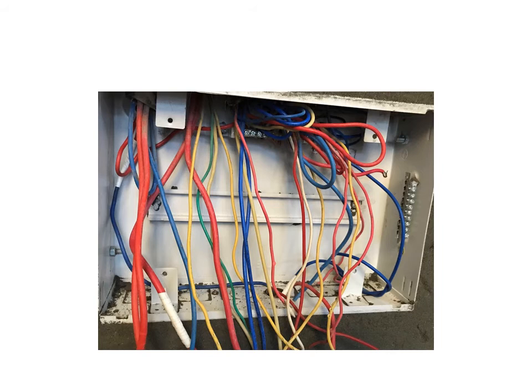So here you can see these connections. On the top, that is the neutral link. In the center you can see this is the DIN rail. All the single pole MCBs will be connected to this DIN rail, and then the connections will be provided to the sub circuits. On the very right side you can see it is the earth link. So the earth wire can be given to any point of this earth link, and then the earth wire can be taken to the sub circuits. So here it is not connected, but on the neutral link, the neutral wire is connected. So the phase is also not connected through MCBs.